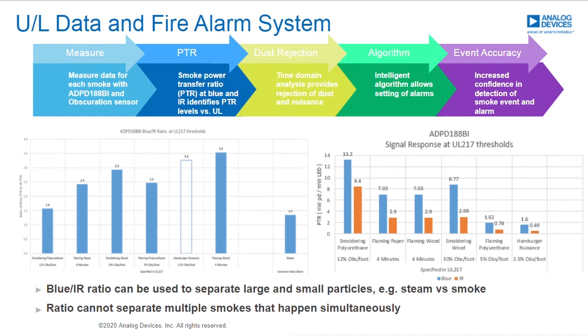One of the issues with just trying to determine ratio is the cooking nuisance test that Grania mentioned earlier, also known as the hamburger test. That test is a way for the standard to force smoke detectors to differentiate between a nuisance source and an actual smoke source. The threshold has to be set high enough that it doesn't alarm on a certain level of hamburger or cooking smoke, but low enough that it will still alarm for any of the valid polyurethane smokes, wood smokes or paper smokes. The threshold has to be low enough that it still alarms for any of the legitimate types of sources you're trying to alarm on.